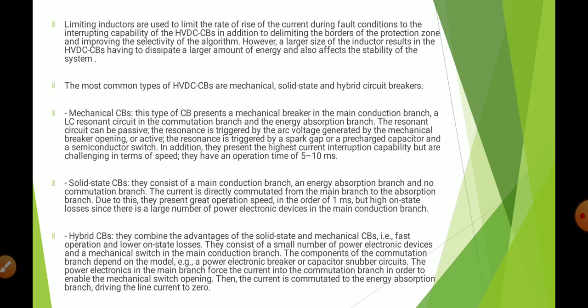Limiting inductors. They are used to limit the rise of current during fault conditions to the interrupting capability of the HVDC circuit breakers, in addition to delimiting the borders of the protection zones and improving the selectivity of the algorithm. However, a larger inductor results in the HVDC circuit breakers having to dissipate a larger amount of energy, and it also affects the stability of the system. The most common types of HVDC circuit breakers are mechanical, solid state circuit breakers, and hybrid circuit breakers.